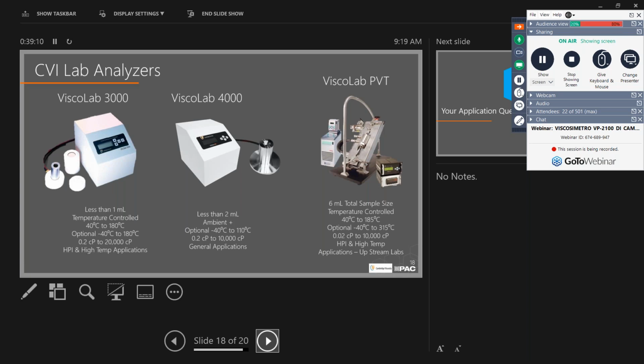So that's very important. It's going to apply the same shear rate to the materials, so you're going to be able to obtain consistent readings even for non-Newtonian fluids. The Viscolab 4000 is one that is used for ambient conditions. It does have a water jacket option, so if you wanted to thermally equilibrate the sample using a temperature-controlled water bath, you could do that, but most commonly it's just used at room temperature.